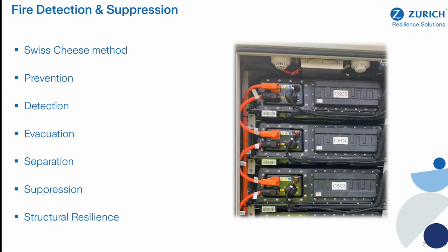So we start with prevention. The first line of defense on a battery storage site is the management system. This continuously monitors the internal temperatures of the batteries. In the event that one is overheating, it will ensure that it's isolated to start with, disconnected from the rest of the group, and then it will start managing via fans and HVAC systems, trying to cool down that battery. That battery might then be set aside, not used anymore until the technicians had a look at it and maybe replaced it. Yeah, that's the prevention side.